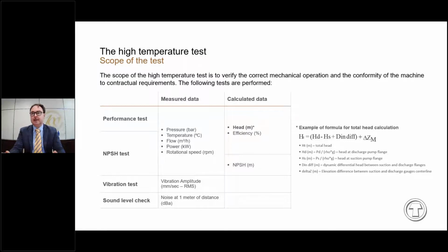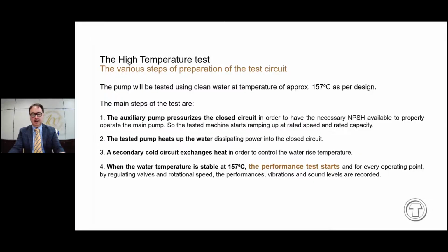During the test, some parameters, as shown in the slide, are measured. For example, pump temperature, flow, and power, and some are calculated, such as total head, efficiency, and NPSH. For example, on the right-hand side of the slide, there is the formula of the total head, where the pressures at the discharge and suction flange are inputs, and the dynamic differential head is also added and calculated as total head. Now, in the next slide, we pass to the high temperature test procedure.